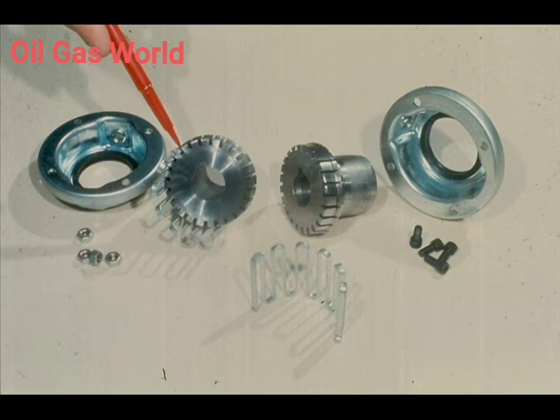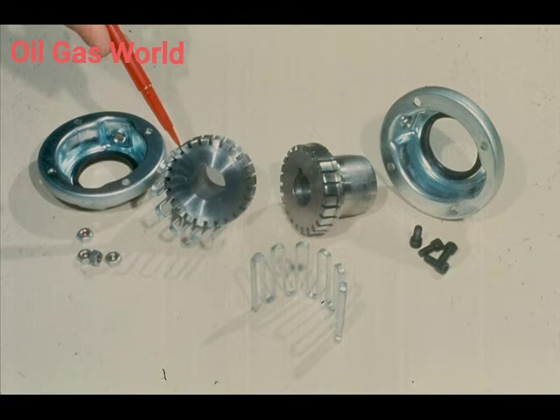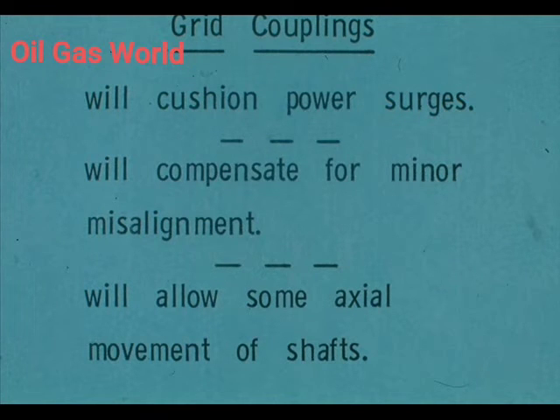This is a grid coupling. It does require lubrication since, as with the gear coupling, there is metal-to-metal contact between the grid and the slots in the hubs. However, the spring steel of the grid adds a number of advantages. A big advantage is that the grid coupling smooths out sudden or abrupt power surges through the spring action of the steel grid. The grid also allows the coupling to compensate for minor misalignment and for some axial movement of the shaft. All in all, the grid coupling is very useful in a wide variety of applications.